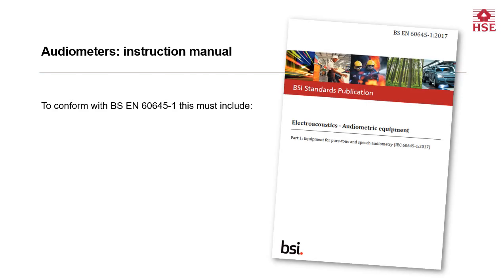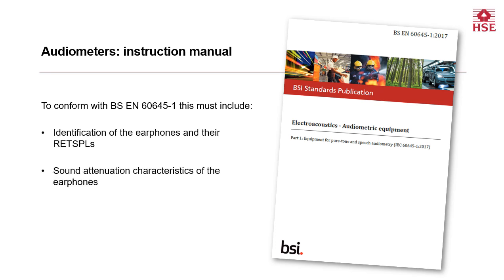Audiometric equipment standard BSEN 60645-1 also requires that the instruction manual includes identification of the earphones and their RETSPLs, the sound attenuation characteristics of the earphones, and maintenance and calibration procedures and schedules. So all of this good stuff should be in the manual, even if you don't have access to it in the standards.